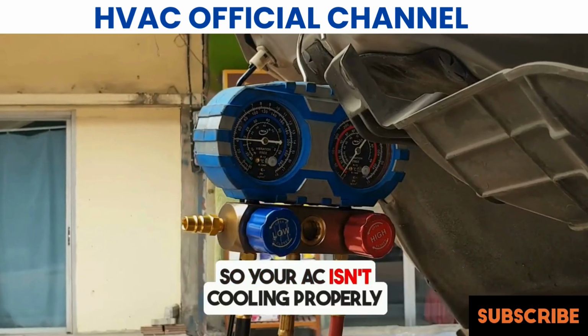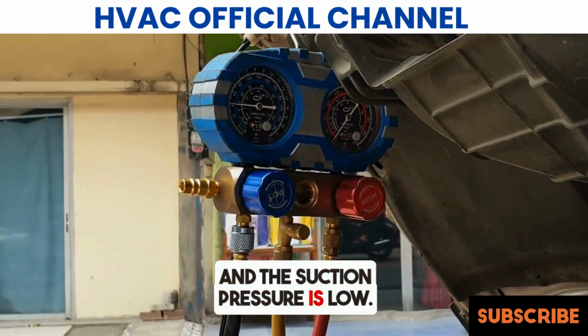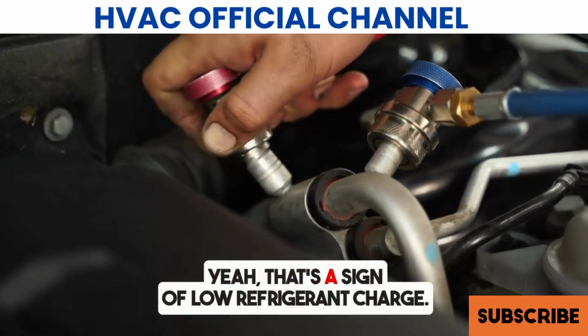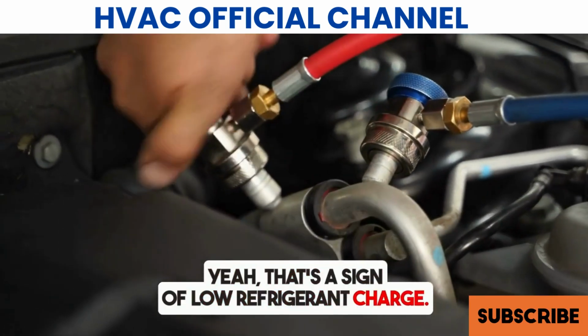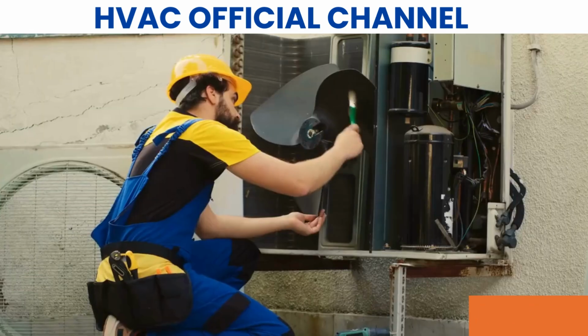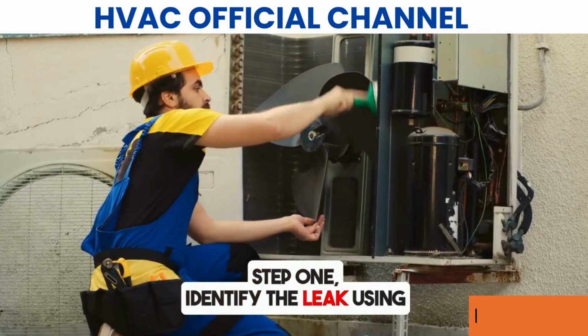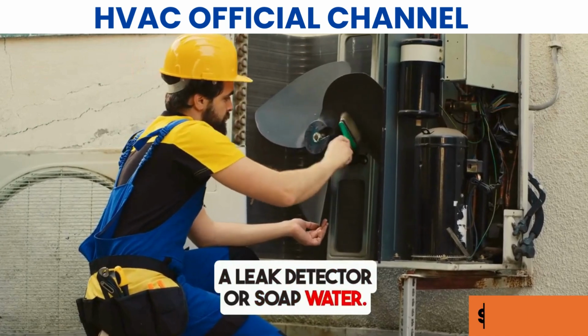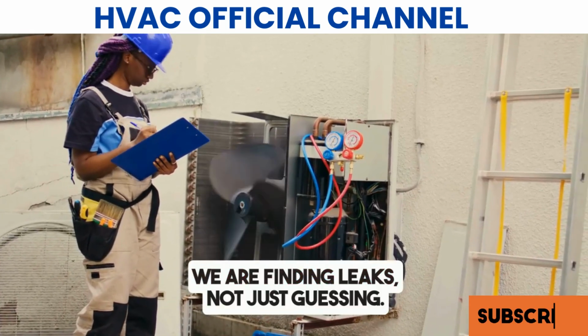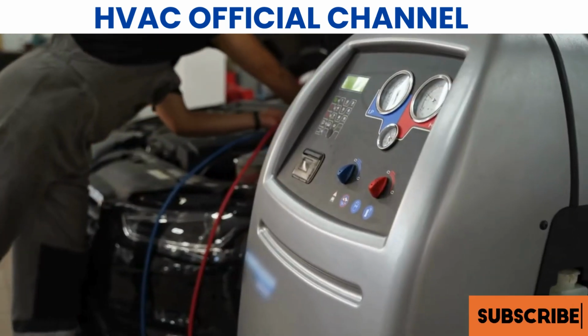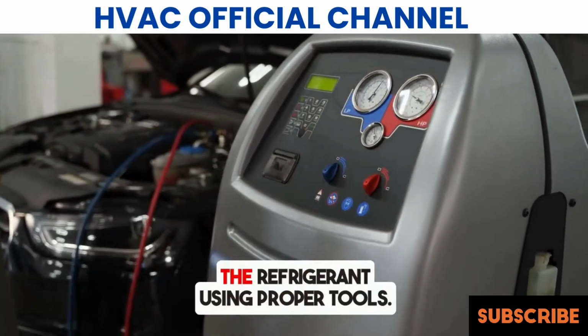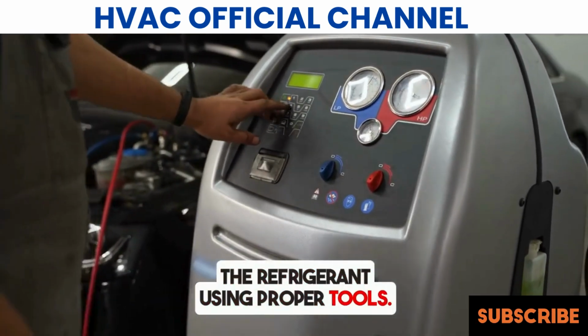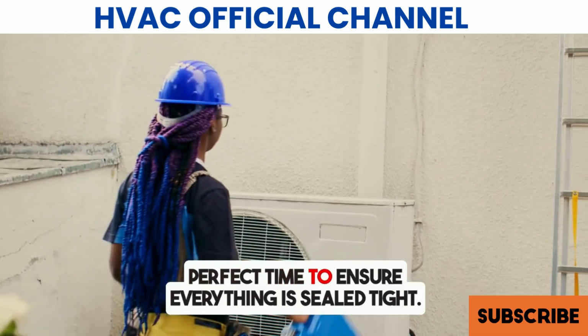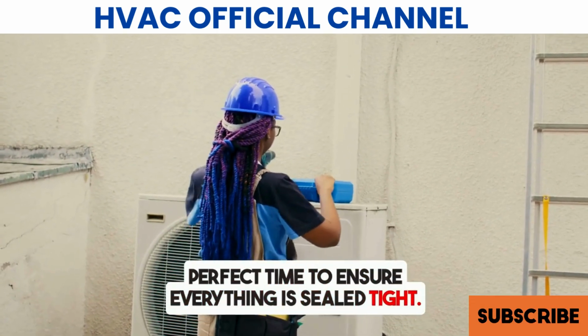So your AC isn't cooling properly and the suction pressure is low? Yeah, that's a sign of low refrigerant charge. Here's how to fix it. Step 1. Identify the leak using a leak detector or soap water. We are finding leaks, not just guessing. Step 2. Fix the leak and recharge the refrigerant using proper tools. Perfect time to ensure everything is sealed tight.